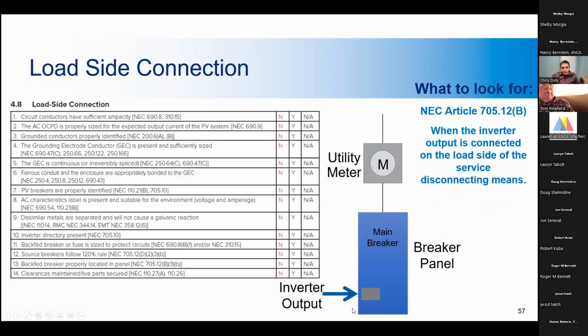All right, so now the interconnections. Here we have kind of an example of a simple drawing of where a load side connection would be. Load side connection is typically a backfeed breaker or a sub panel. And this is where the inverter output is connected on the load side of the service. The service disconnecting means, like I said, is typically backfeed breakers, and they're typically located at the opposite side of the panel, the electrical panel, so as not to overload the bus bar.